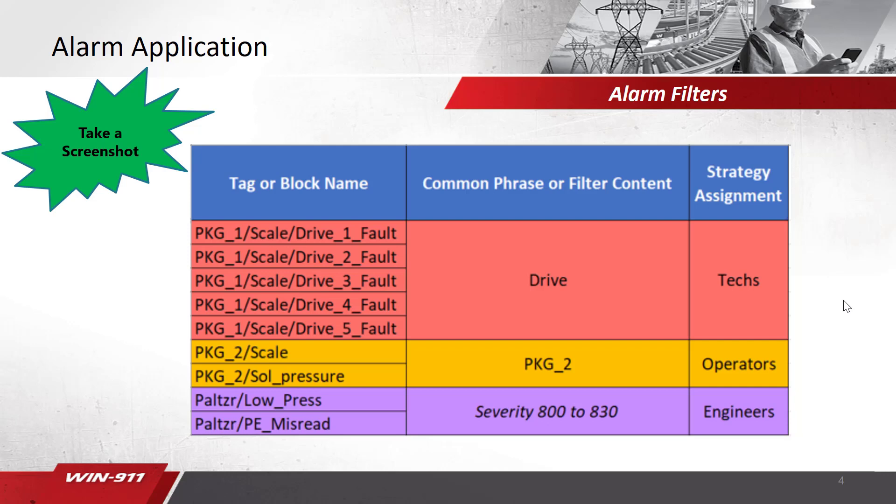So this first list of items in the red, these are items I want to send to the tech. These are all drive fault, so I'm going to filter on the word drive for my alarm subscription filter. The next set in orange there, these are alarms I want to go to the operators. I'm going to filter on the class for PKG2. And then finally, we can filter on severity. These are alarms we want to go to the engineer. So we're going to filter on severity between 800 to 830.